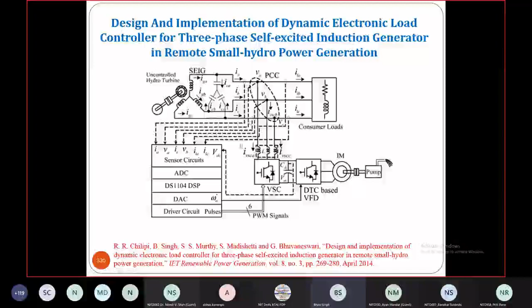And it consumes whatever remaining power the load is not consuming, it takes that power, so that frequency is also regulated here. So this is the typical control, and we use an available drive, and for frequency control the drive speed is controlled so that it can consume different power for pumping different amounts of water, for an overhead tank or something like that. So these are typical results, and it feeds a variety of non-linear loads, and it works very well. The voltage THD is only 0.7%, where your load current THD is 15%.